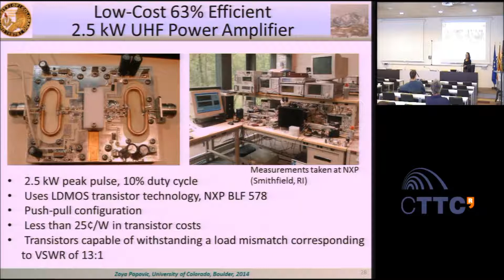Anyway, he got a lot of press, but the ultimate result was we got a lot more devices, so we made a bunch of amplifiers. So this shows, you always worry when you do this high power, you worry what's heating up the most, where your weak link is, so it's a good idea to take a thermal image. And this shows that the device was not heating. Look, it's blue. But there's emissivity here too, but we tried to calibrate for that. But the capacitors were heating. The coax is doing well. The capacitors were really heating. And so in the real amplifiers that they use in the field now, we invested a little more money and bought some better high voltage capacitors so they're not heating as much.